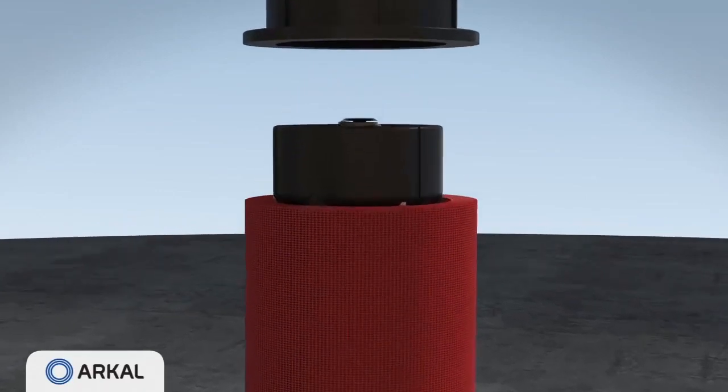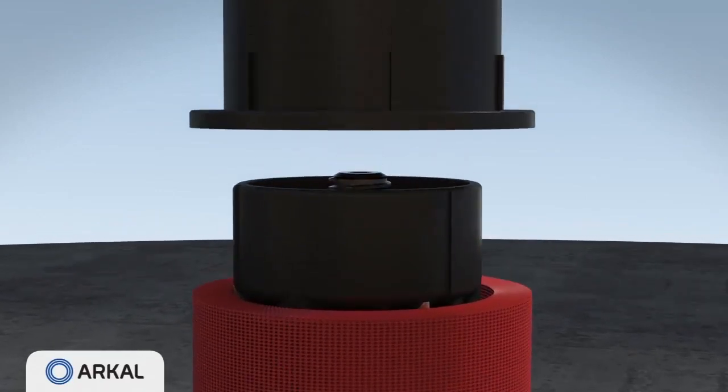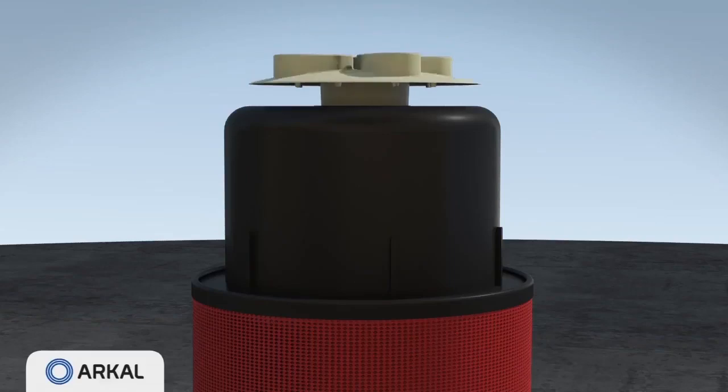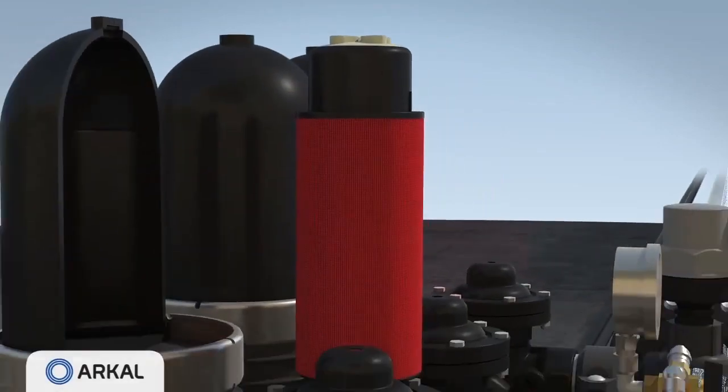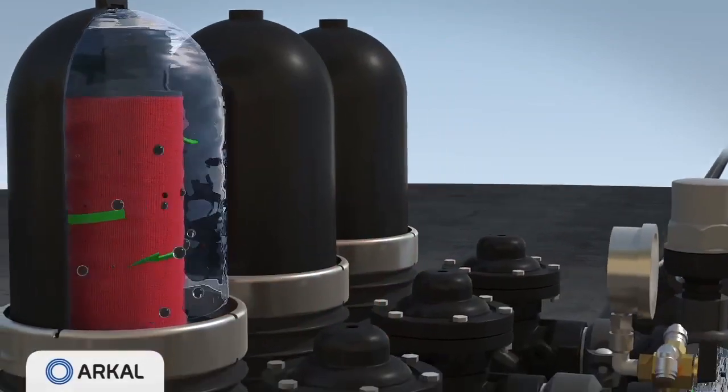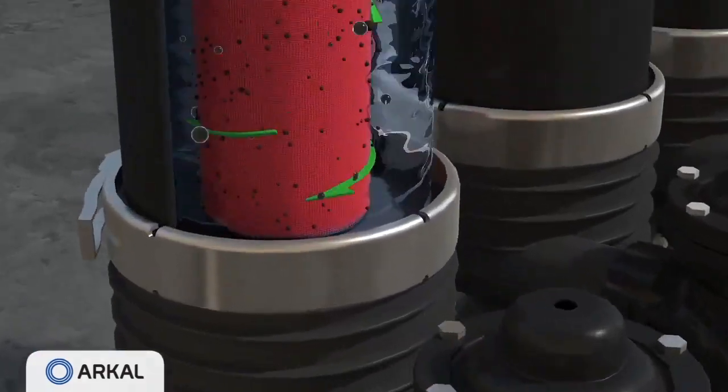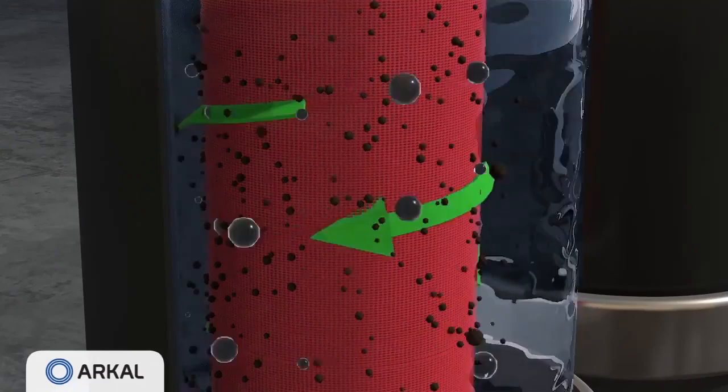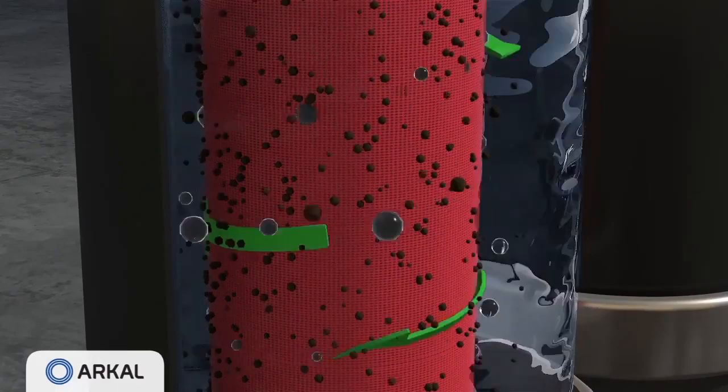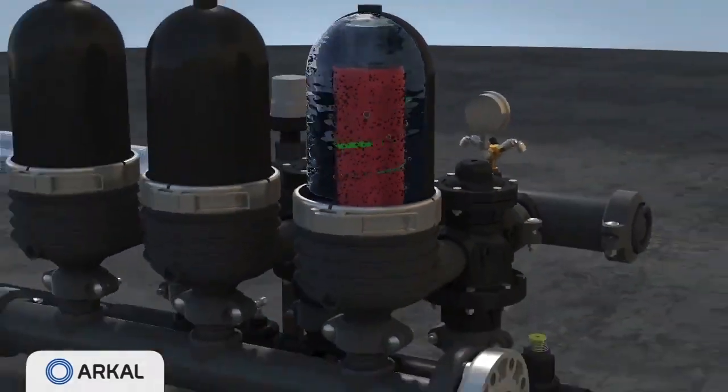During filtration, the force of the spring and the differential pressure firmly compresses the discs together. Water permeates from the outer diameter to the inner diameter of the filter element and suspended solids are trapped on and within the discs matrix. Filtered water flows through the filter outlet port.